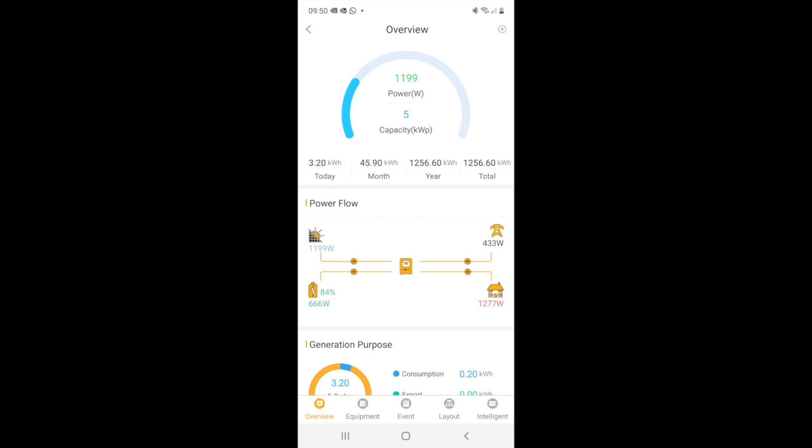Now have a look at the power flow diagram after we've done the factory reset. So we've got 1199 watts of power coming from solar, we've got 666 going to the battery, 433 from the grid and 1277 to the load.